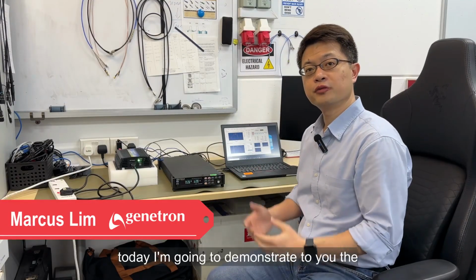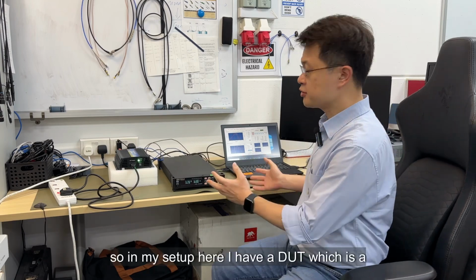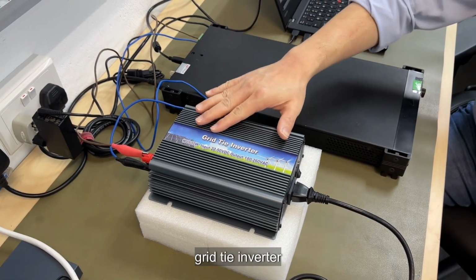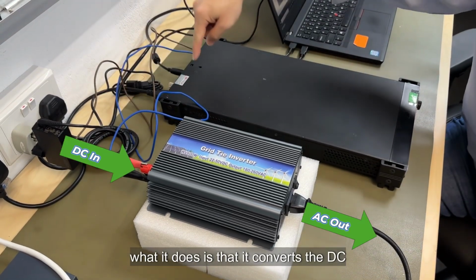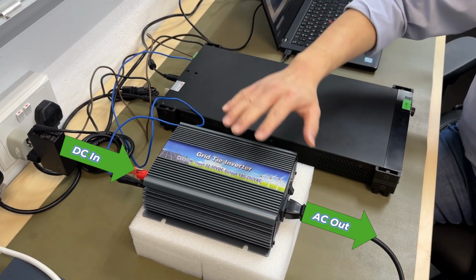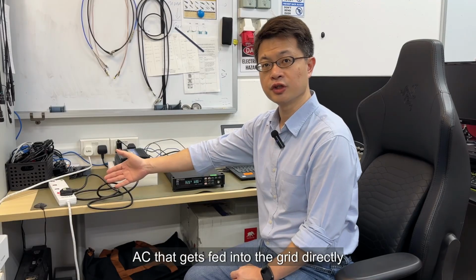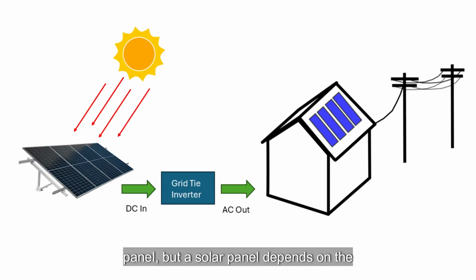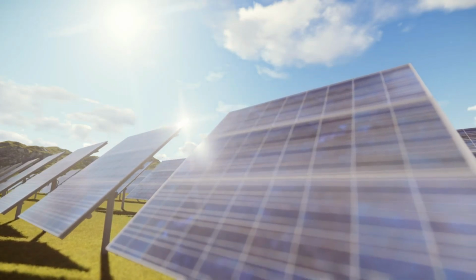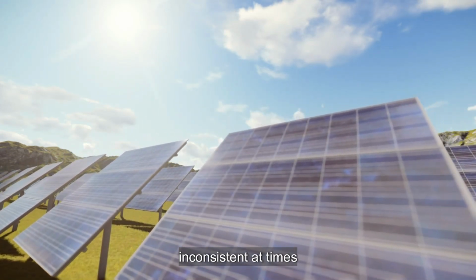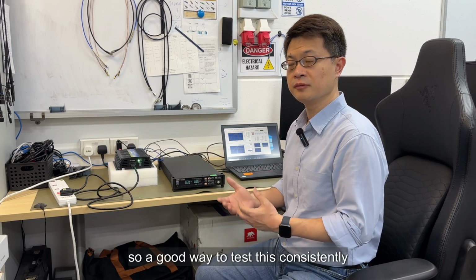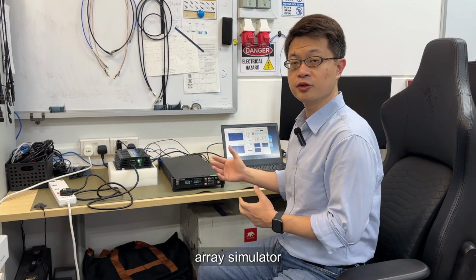Hi, today I'm going to demonstrate to you the use of the iTech Solar Array Simulator solution to test grid tie inverters. So in my setup here, I have a DUT, which is a grid tie inverter. What it does is that it converts the DC power from the solar panel into AC that gets fed into the grid directly. Now, in order to test this grid tie inverter, you would need to connect it to a solar panel, but a solar panel depends on the irradiance and the temperature, which is pretty inconsistent at times. So a good way to test this consistently is to use a solar array simulator.